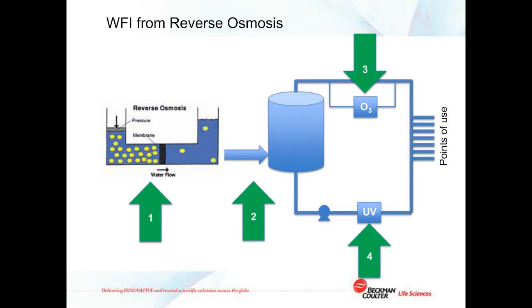As the ozone is considered an added substance, it must be removed before the water is used. And this is achieved using an ultraviolet light, which is an ozone destruct system in the water loop itself. As the water leaves the storage tank, the ozone is destroyed using the UV light. Ozone breaks down very rapidly in the presence of UV light and is prevented from entering the water loop.